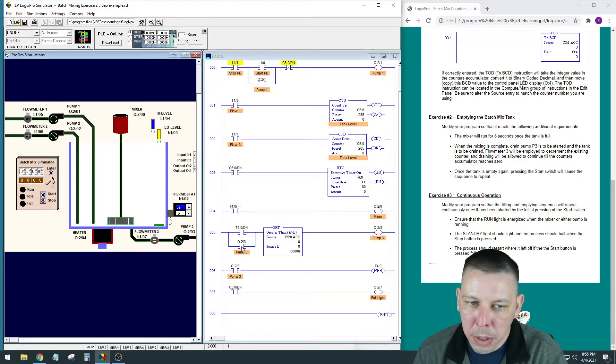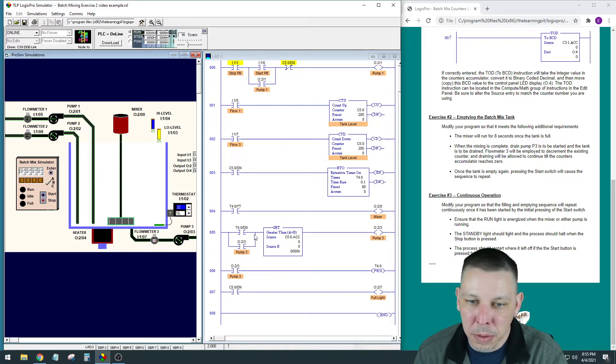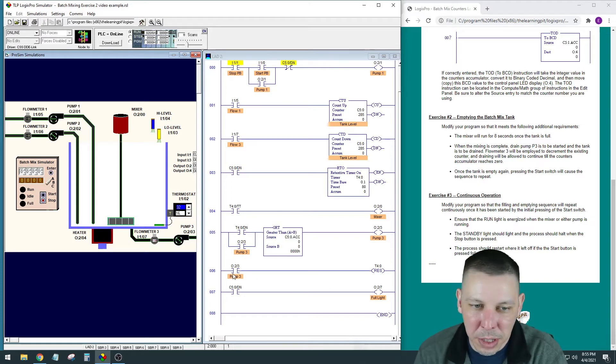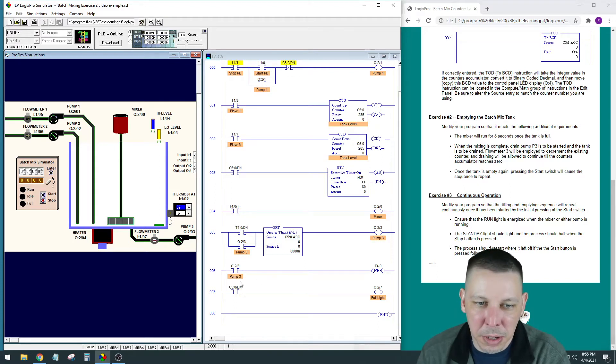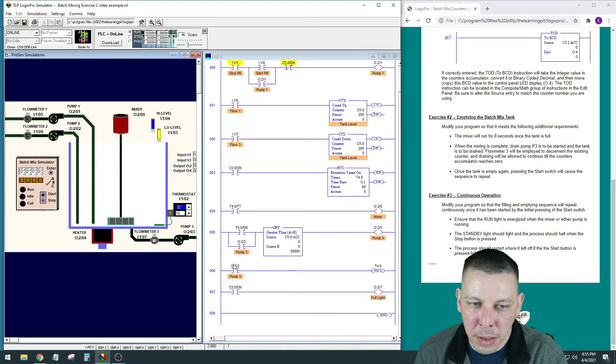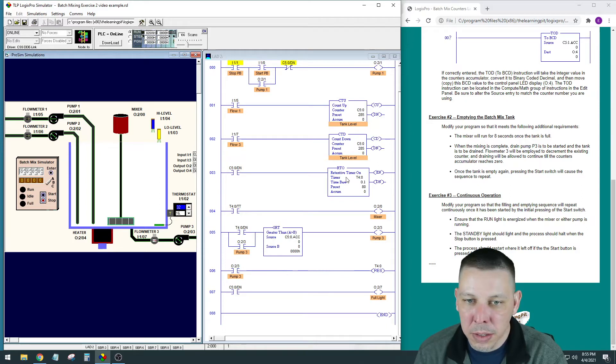Pump 3 would latch itself in down here around that T4.0 done bit, because the next time it comes through it's going to be erased—it's not going to be done anymore. It would be a zero instead of one. So this pump locks itself in immediately, and then whenever this pump is turned on, the output 2/3 pump 3 goes and resets T4.0.